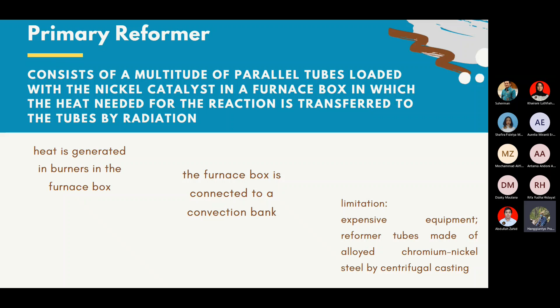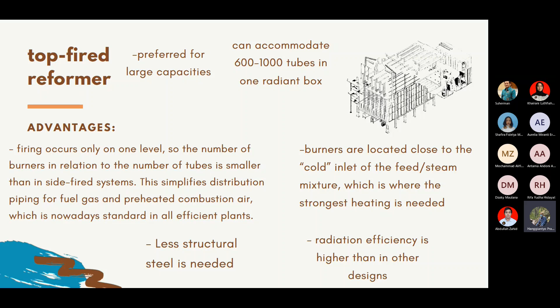Top-fired reformer. The advantage is that firing occurs only on one level, so the number of burners in relation to the number of tubes is smaller than in the side-fired system. This simplifies distribution piping for fuel gas and preheated combustion air, and is nowadays standard in all ammonia plants. Less structural steel is needed. The burners are located close to the cold inlet of the feed or steam mixture, which is where the strongest heating is needed. Radiation efficiency is higher than in other designs.